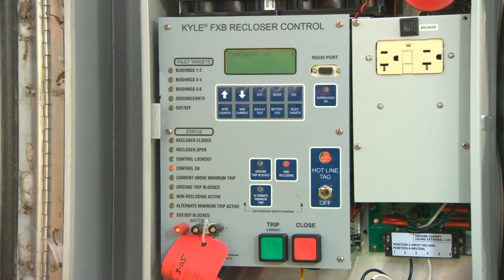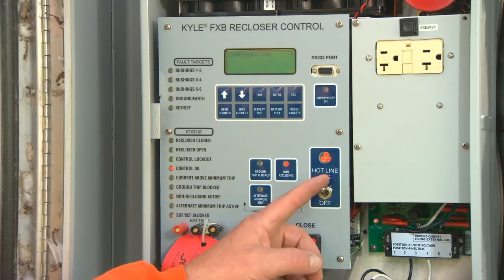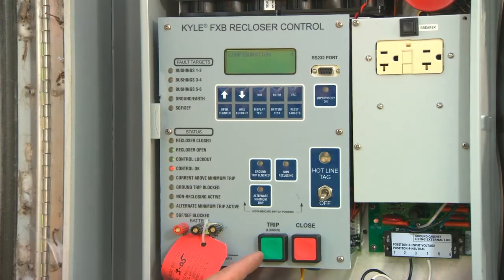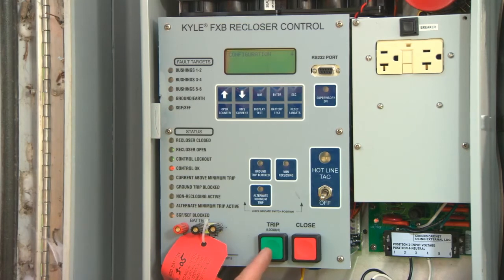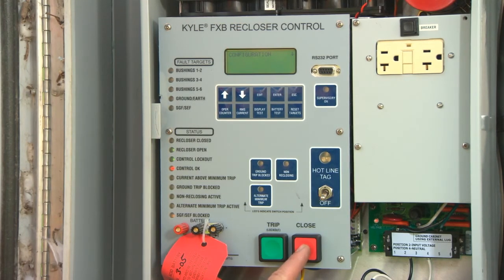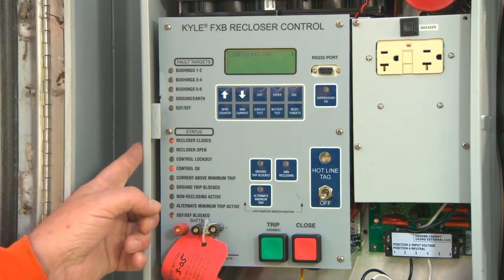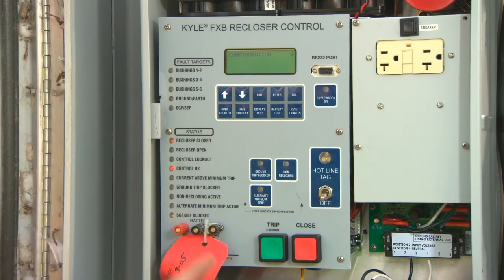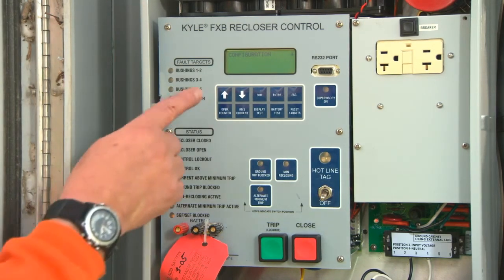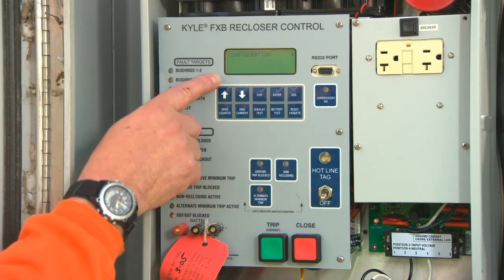To remove the hotline tag, move the switch down, and all of the indicator LEDs will return to their normal state. Along the bottom of the unit, we have the green trip and the red close buttons. After pushing the close button, you will notice the status indicator LED for recloser closed change state. The recloser is now closed. To trip, simply press the trip button, causing the recloser to trip open. The green recloser open and control lockout LEDs on the left side will illuminate.